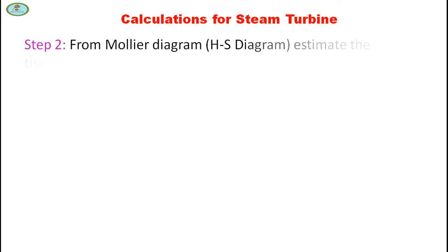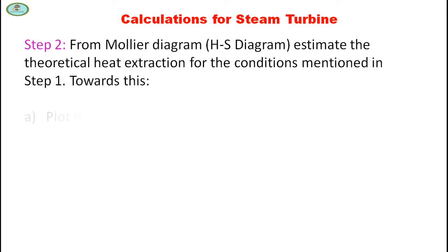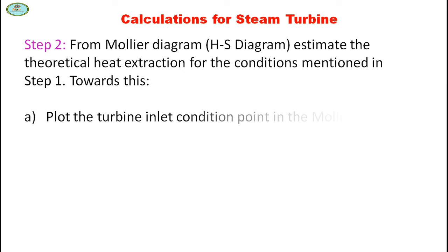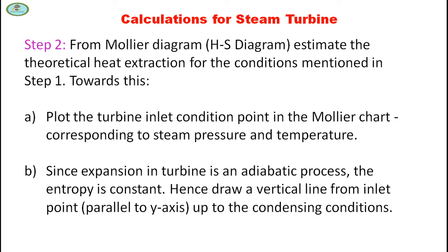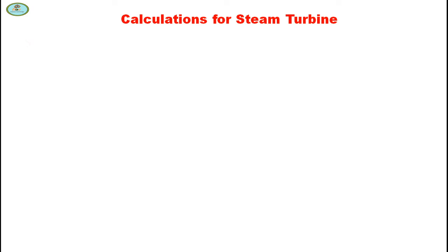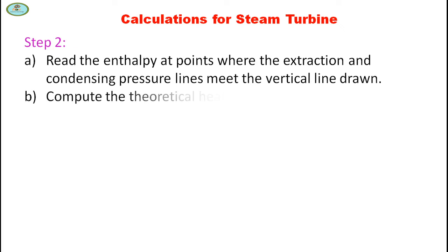In Step 2, from the Mollier diagram, estimate the theoretical heat extraction from the conditions mentioned in Step 1. Plot the turbine inlet condition point on the Mollier chart corresponding to steam pressure and temperature. Since expansion in a turbine is an adiabatic process, entropy is constant. Hence, draw a vertical line from the inlet point up to the condensing conditions, and read the enthalpy at the point where the extraction and condensing pressure lines meet the vertical line drawn. Compute the theoretical heat drop for each stage of expansion.